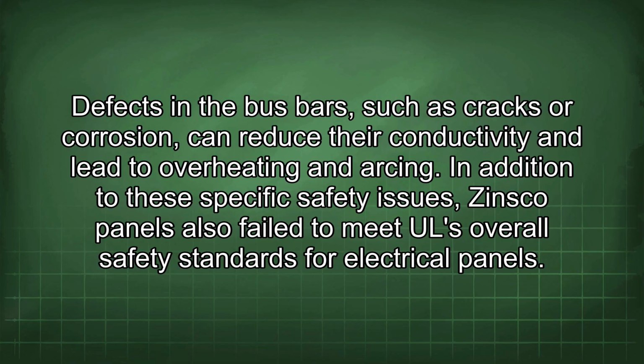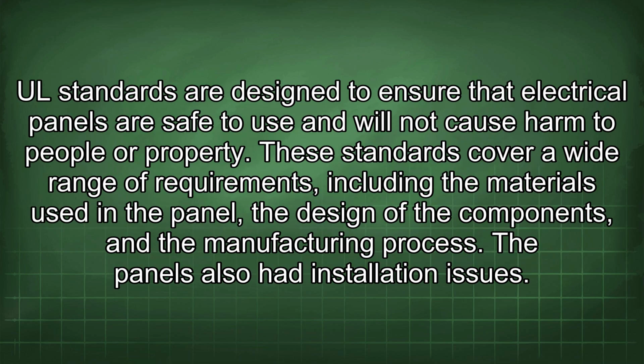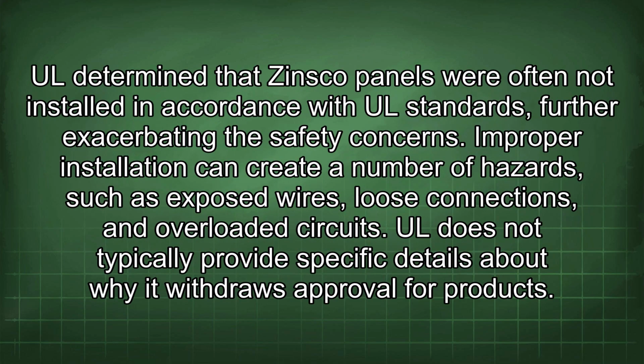In addition to these specific safety issues, Zinsco panels also failed to meet UL overall safety standards for electrical panels. UL standards are designed to ensure that electrical panels are safe to use and will not cause harm to people or property. These standards cover a wide range of requirements, including the materials used in the panel, the design of the components, and the manufacturing process. The panels also had installation issues. UL determined that Zinsco panels were often not installed in accordance with UL standards, further exacerbating the safety concerns. Improper installation can create a number of hazards, such as exposed wires, loose connections, and overloaded circuits.